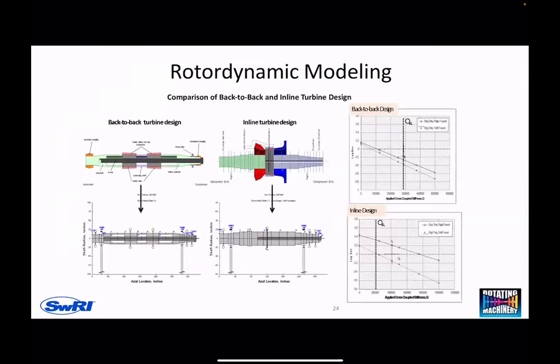As mentioned before, we also evaluated the rotor dynamics. We did multiple designs with a back-to-back design, a straight-through turbine design, and looked at how this would behave rotor dynamically. Typically, aerodynamics and rotor dynamics do not get along - as shown in the chart earlier, the more stages, the higher the aero efficiency, but the more stages, the worse the turbine performs rotor dynamically.